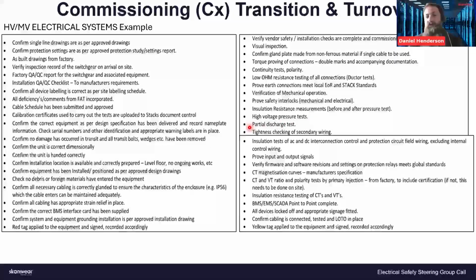But all these tests ideally should pick that up. Partial discharge test, fine, but that would really be after first power - you're not really going to pick anything up when it hasn't been energized yet. If all of these things are conducted, they should significantly reduce the chance of flashover on first energization, and I don't see any reason why we should still be having them if we're following something like this.